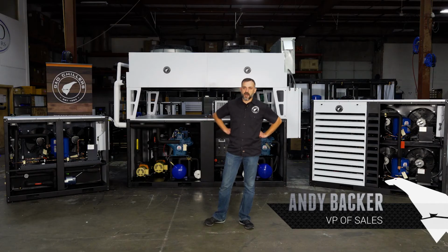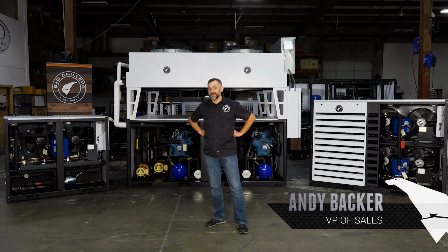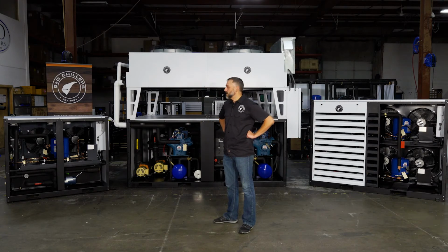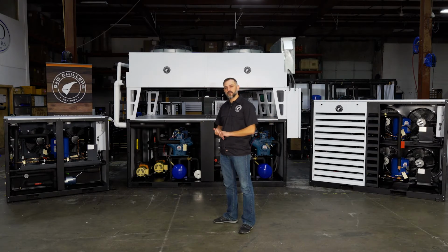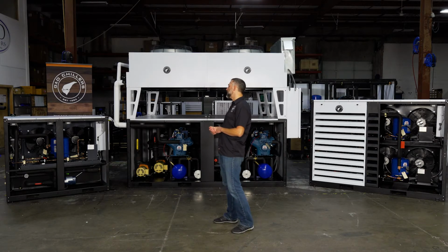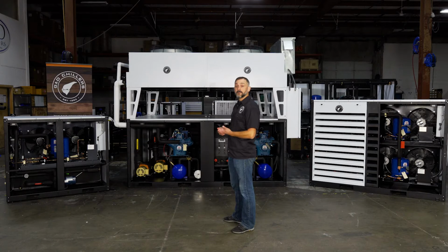You as the end user, the operator, your staff, your team, it's not much. I mean, the biggest thing, the number one cause of chiller failure is improper glycol mixture. We design our chillers to be run at a 35% by volume mixture of glycol and water. We recommend people do that.